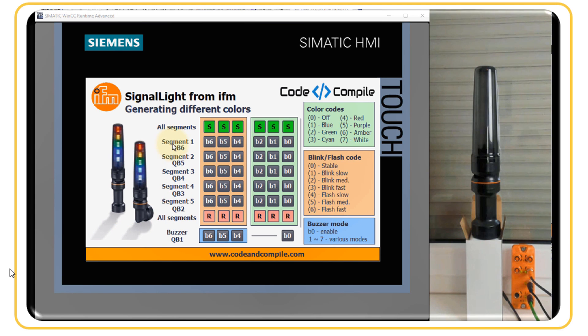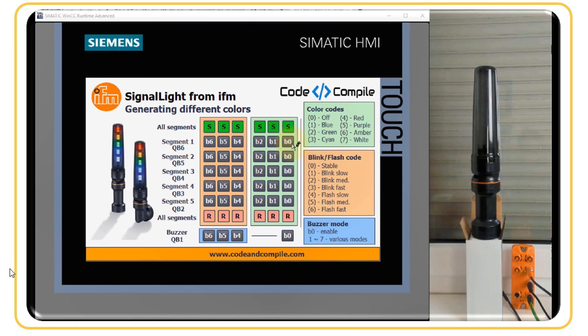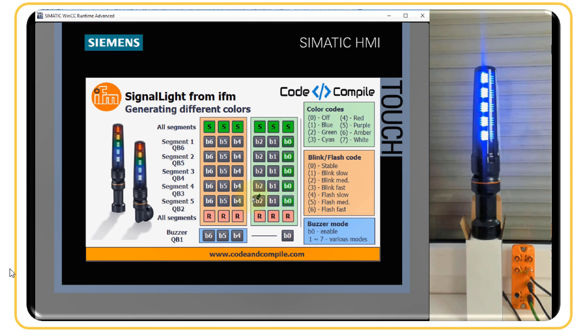On the HMI screen we have various bits defined for the signal light segments. The signal lamp has five segments, and we have specified bytes for these segments split into bits. When all bits are zero, the lights are off. To turn on blue light in segment one, the first bit should be true. When energized, the blue light turns on.